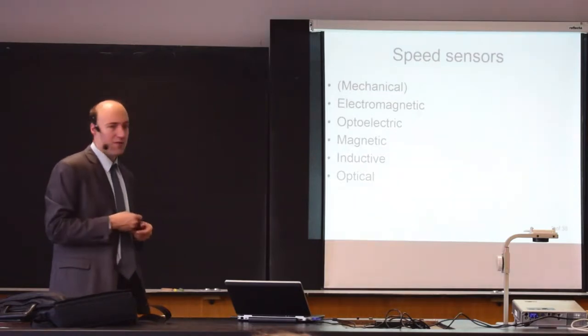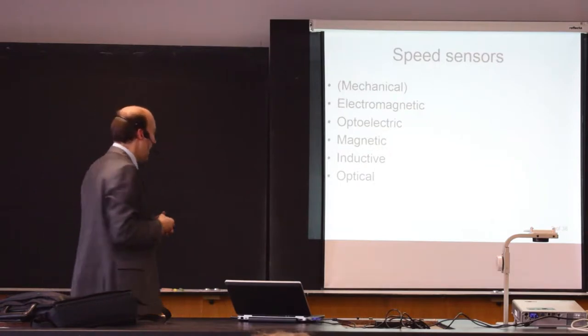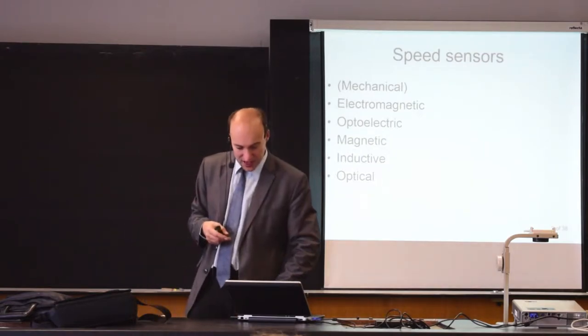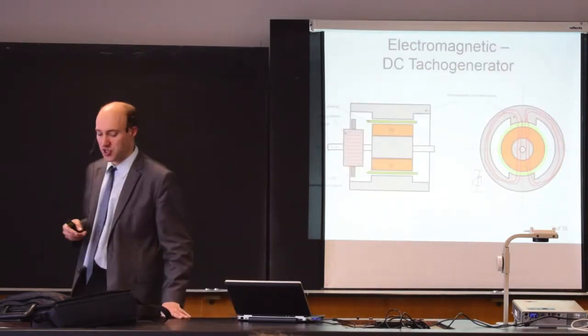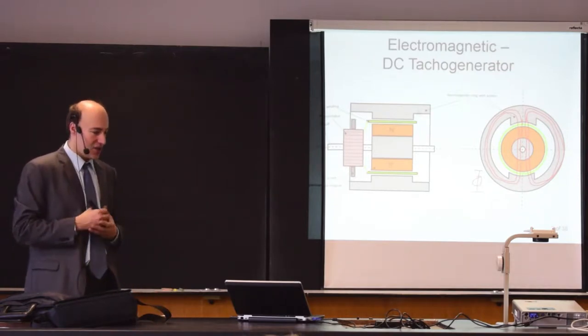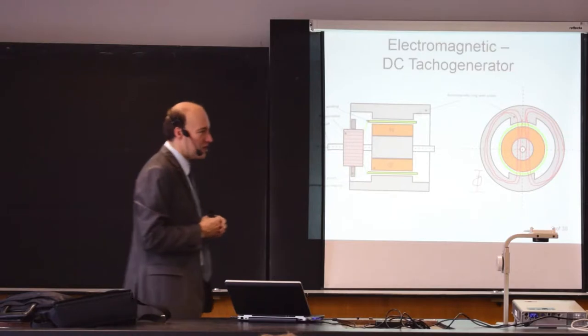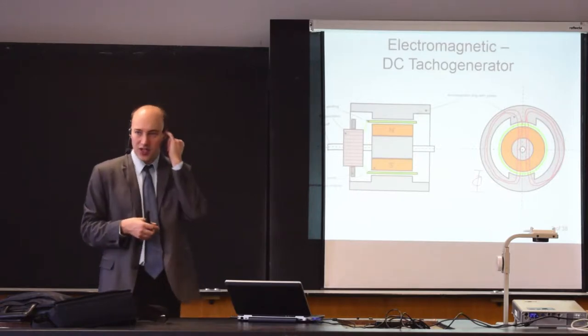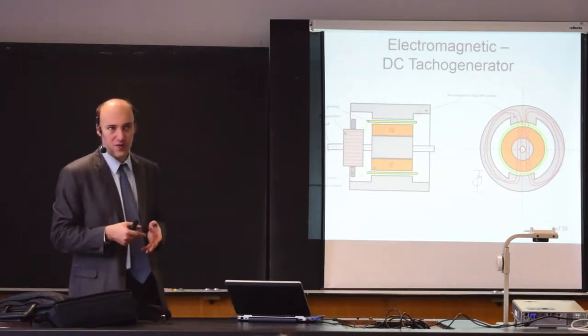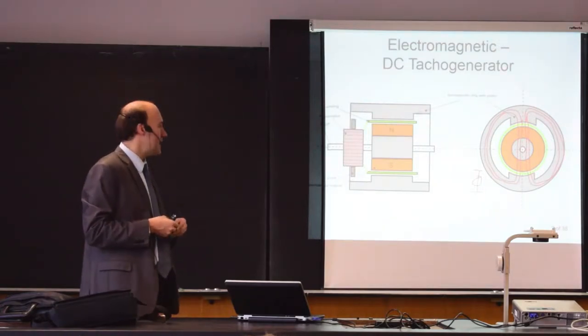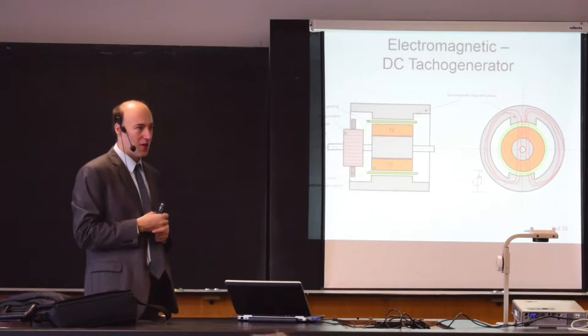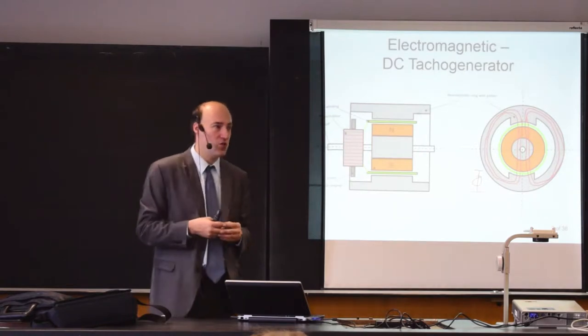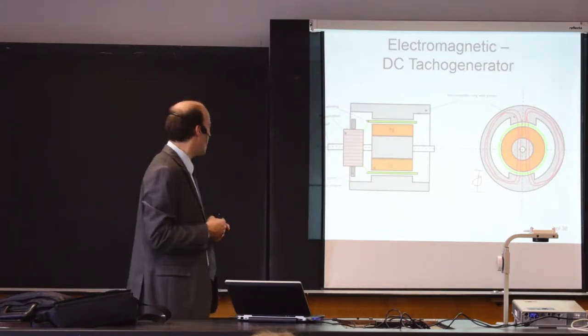We can also measure speed with pure optical sensors, and I'll show you just one example: the stroboscope. Let's start with the electromagnetic sensor called a DC tacho generator. A DC tacho generator is essentially an electric machine — a generator that produces a voltage — and the amplitude of this voltage is a function of the speed of rotation. It is something like an electric generator, but we will not use it to create power; we use it simply to create a voltage that we measure.